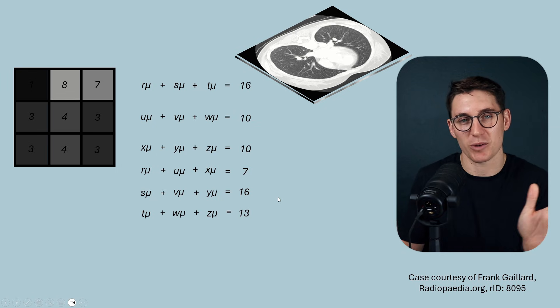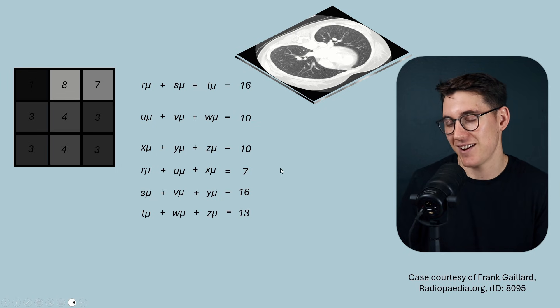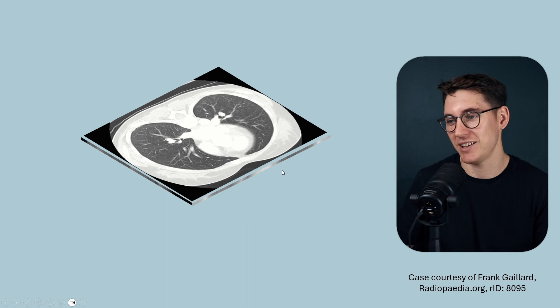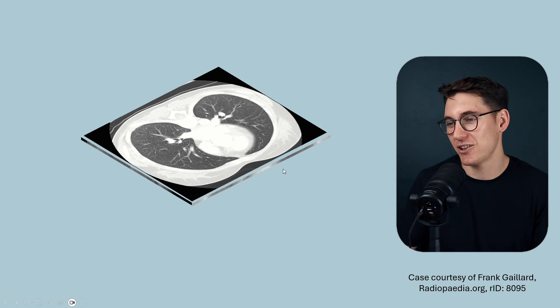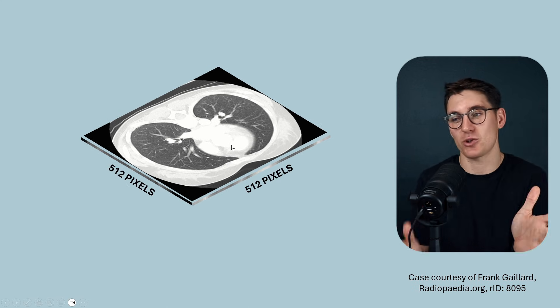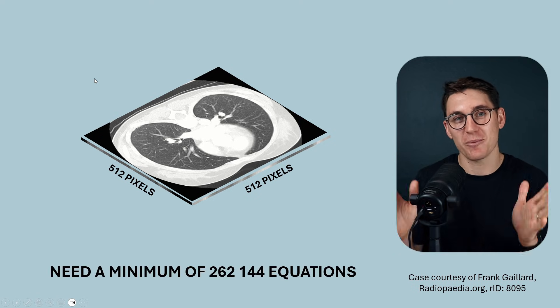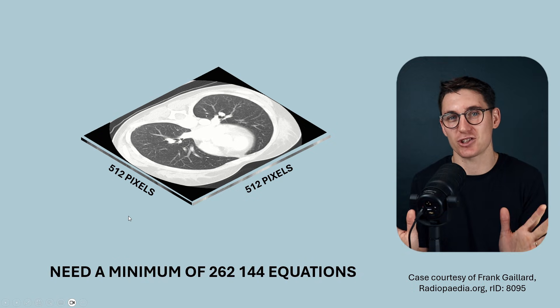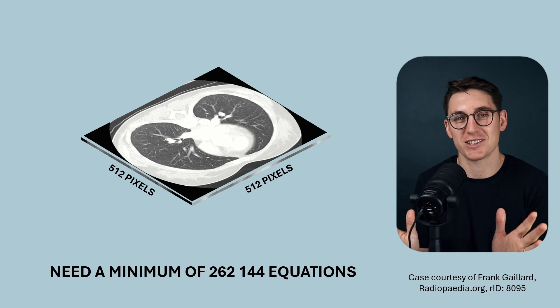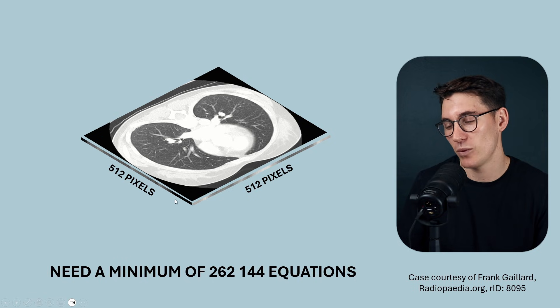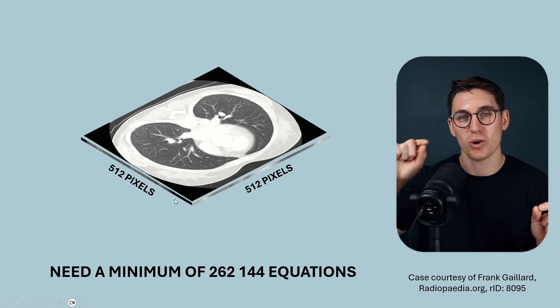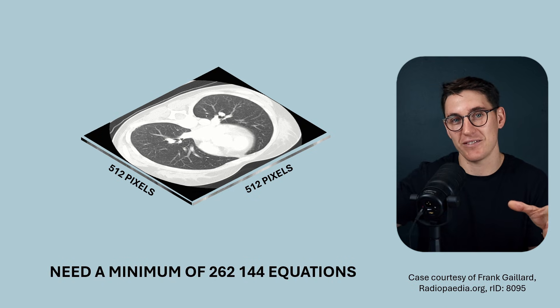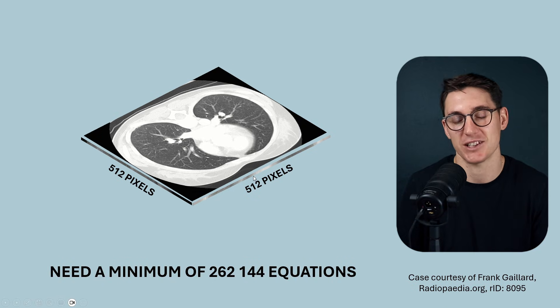How many angles would we need? For an image with 512 by 512 pixels, we would need to generate more than a quarter million equations — over 262,000 simultaneous equations. You can see why it's called computed tomography: no human could feasibly solve that. We're going to need at least 512 different views if we've got 512 detectors.